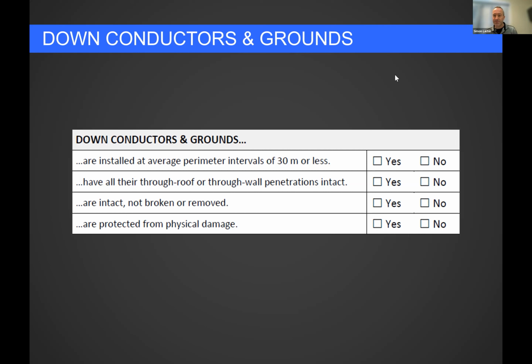Yes, Martin. So just a question, because in your little checkpoint there, it doesn't seem to show 12-016 where our code talks about, because I'm assuming a lot of this is coming from your standard, but our code says also that where lightning down conductors are installed, electrical wiring shall, where practicable, be kept at least 2 meters from such conductors.